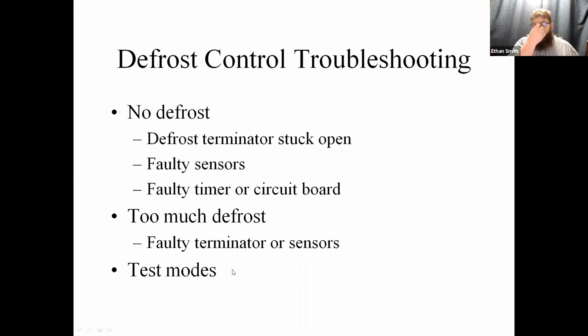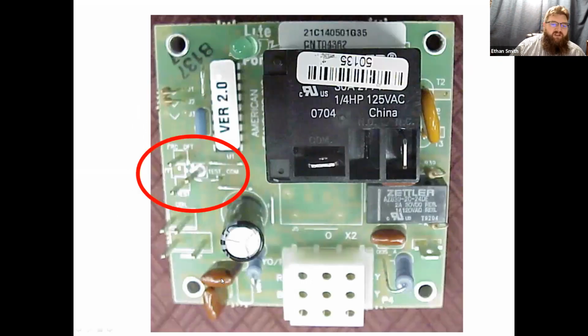So don't be afraid of that though, guys. Get in there, test the sensors. Nine times out of 10, if you've got a defrost problem and it's not related to your humidity, it's going to be a bad sensor. So get the charts out, look at the sensors.